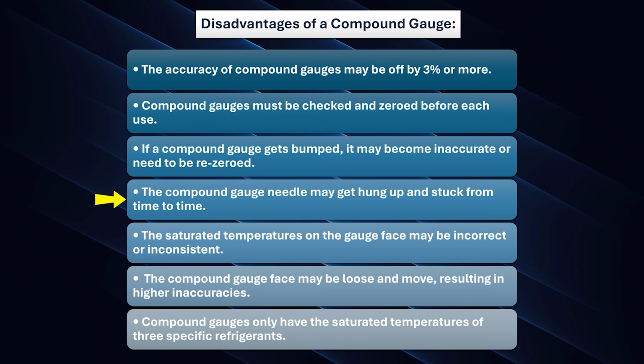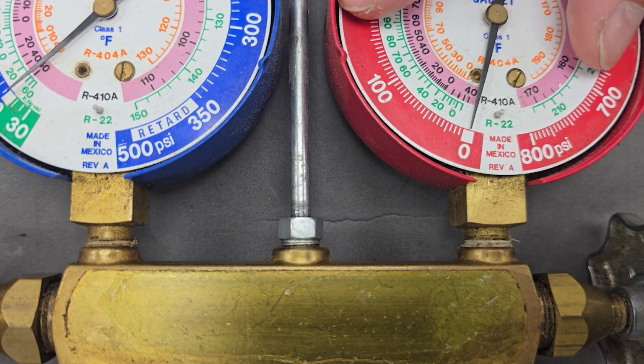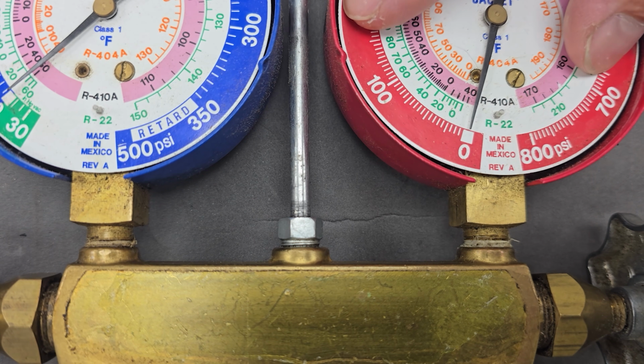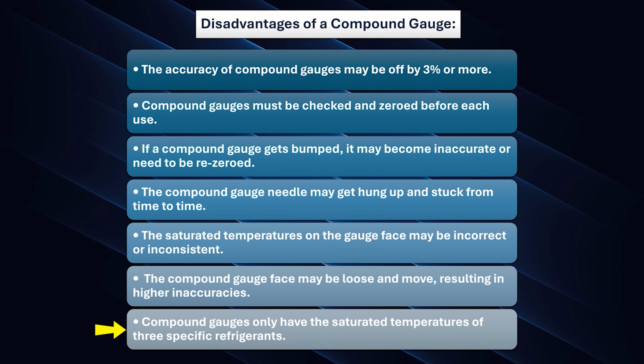The compound gauge needle may get hung up and stuck from time to time. The saturated temperatures on the gauge face may be incorrect or inconsistent. The compound gauge face may be loose and move, resulting in higher inaccuracies. Compound gauges only have the saturated temperatures of 3 specific refrigerants.